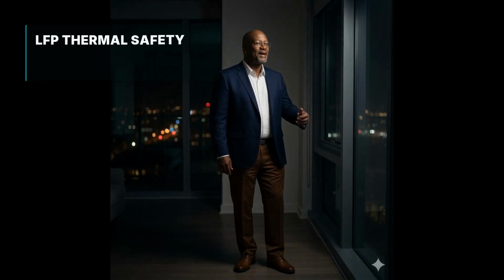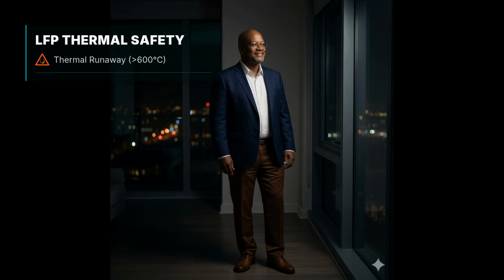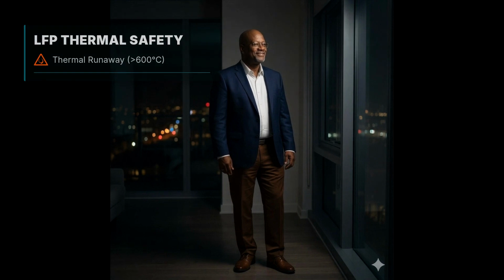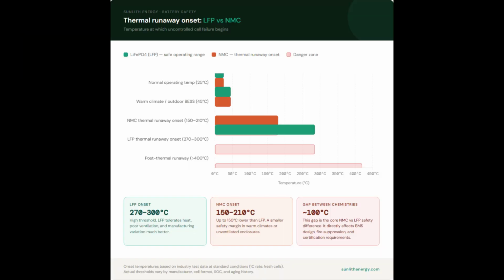Safety in a lithium-ion battery room requires specific design decisions, not general assumptions. We must address the risk of thermal runaway, an exothermic reaction that can exceed 600 degrees Celsius and lead to catastrophic failure if not managed. LFP chemistry has a much higher thermal stability threshold than NMC. While thermal runaway releases flammable gases, the threshold is higher and propagation is slower in LFP, giving our suppression systems critical time to respond and contain the event.